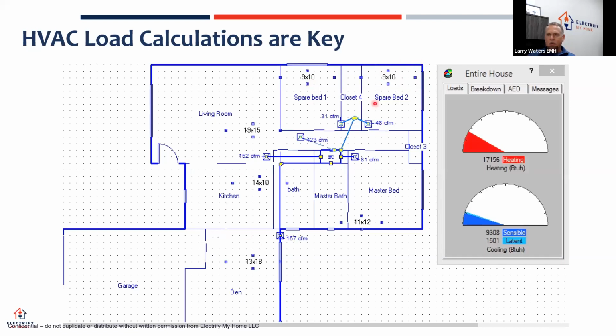This particular house that we did, we installed R49 insulation in the attic. And then they had new windows installed when we put this in. The system we took out of here was 3 times larger than what we ended up putting back. This is a 1,500 square foot house with 18,000 BTU, 1.5 tons of cooling and heating in it. But those 1.5 ton units can do way more than that because they're inverters, so they can ramp up. But you want to make sure you're doing load calculations with these.